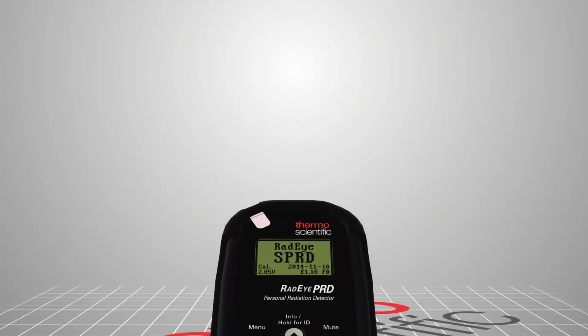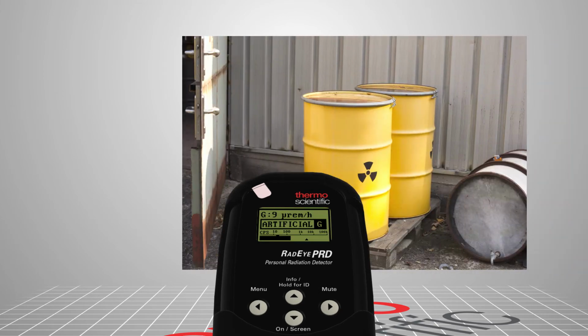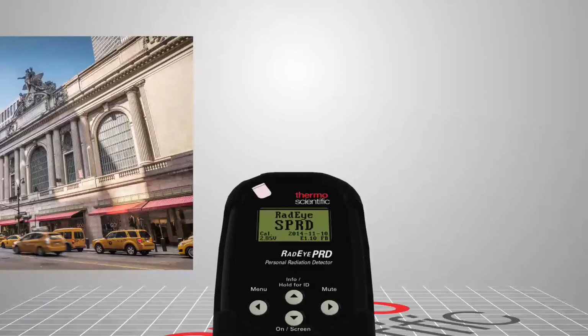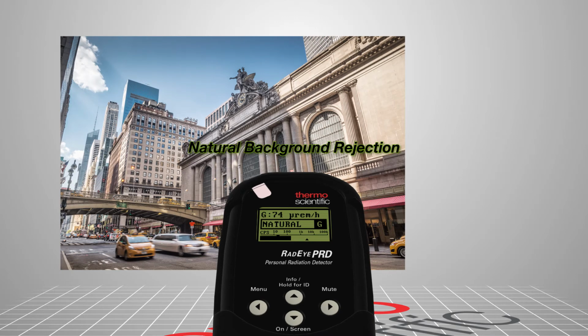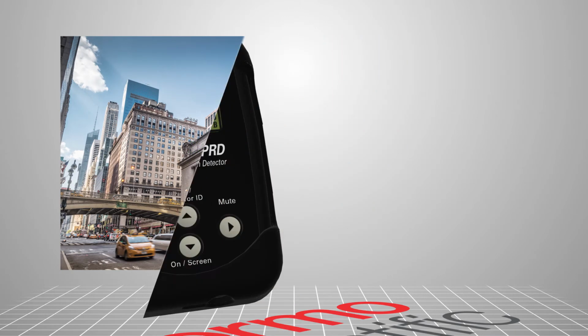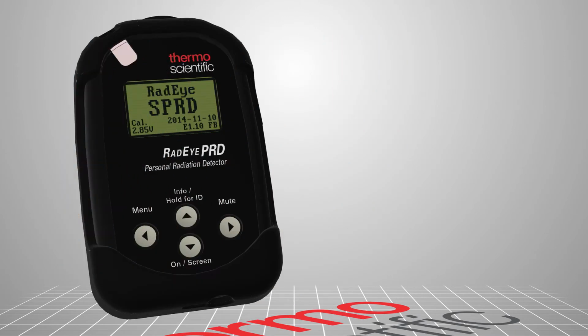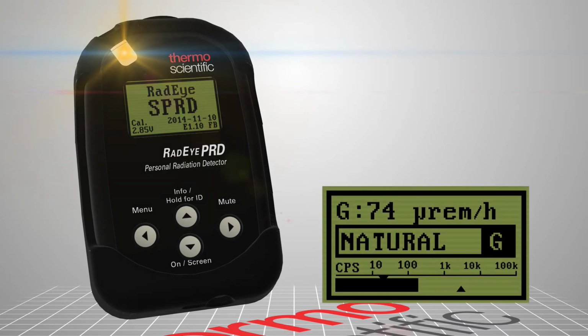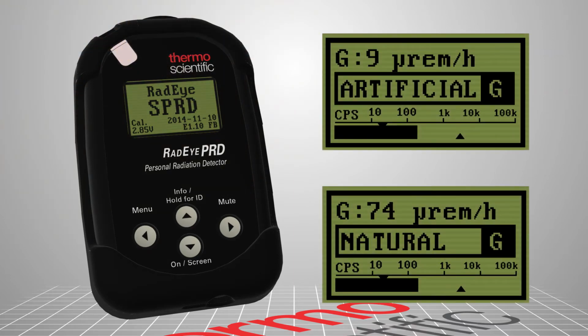The RadEye SPRD automatically determines the radiation type as either artificial or natural, with its unique natural background rejection, or NBR, capability. When configured as a basic PRD, alarms will be accompanied with either natural or artificial displayed on the screen. The unit constantly adjusts to varying levels of natural background radiation, which minimizes false alarms while maintaining detection sensitivity for artificial radiation. Alternatively, the RadEye SPRD can be configured for simplified nuclide identification.